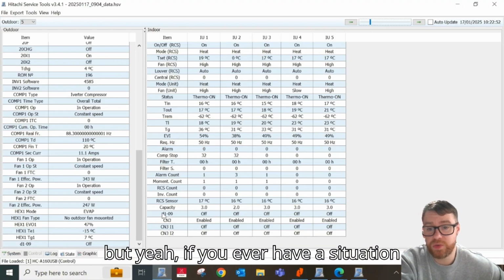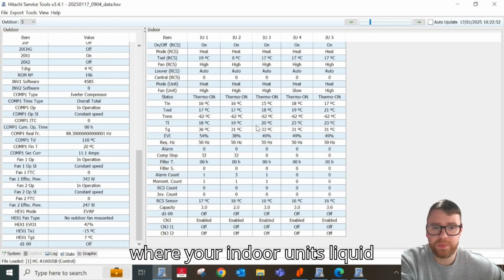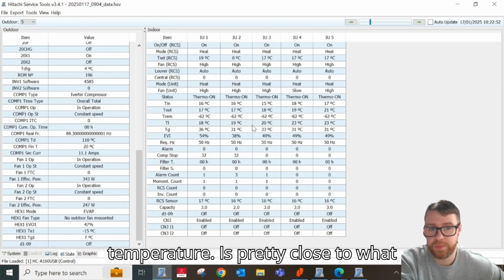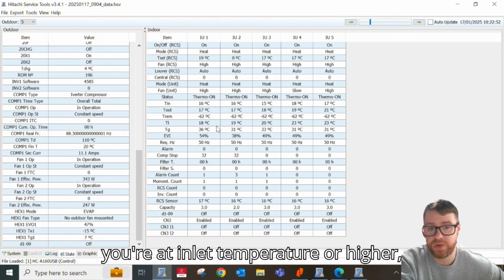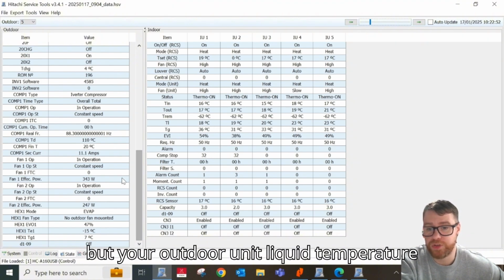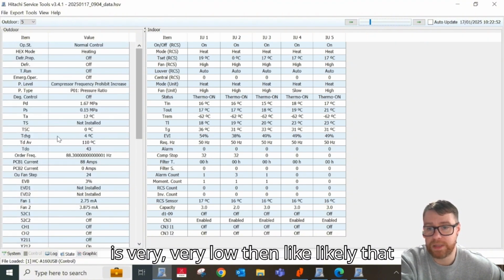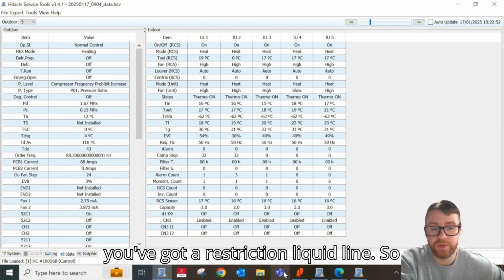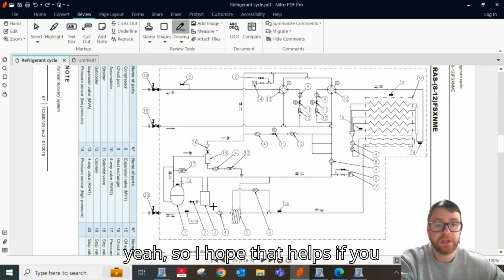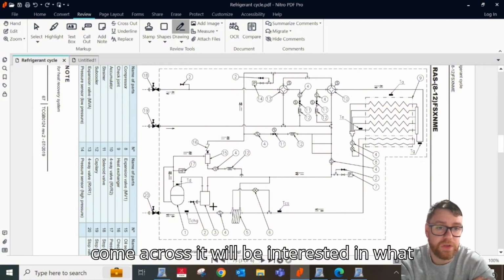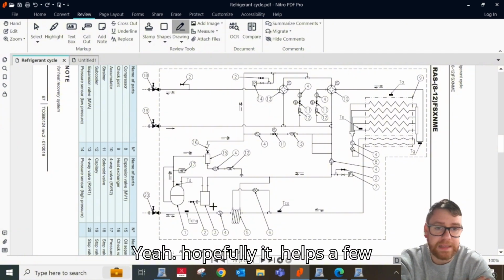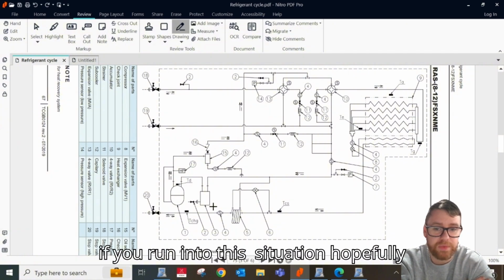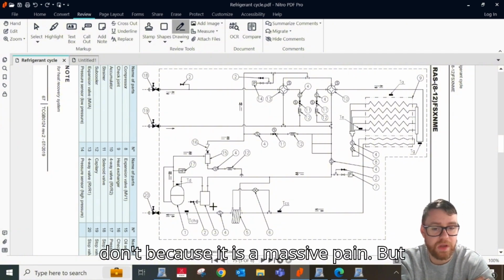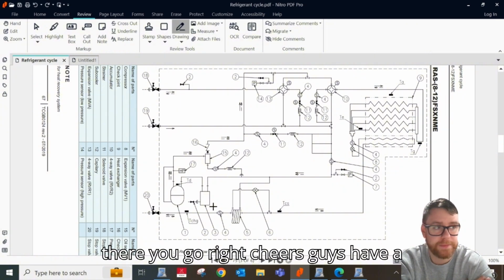But yeah, if you ever have a situation where your indoor unit's liquid temperature is pretty close to what your air inlet temperature is or higher, but your outdoor unit liquid temperature is very, very low, then likely you've got a restriction on your liquid line. So yeah, I hope that helps. If you come across it, it'll be interesting to hear whatever things you've picked up. But yeah, hopefully that helps if you've ever run into that situation. Hopefully you don't, because it is a massive pain, but there you go.